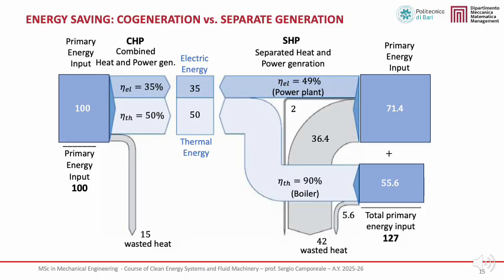As a result, the total primary energy input is approximately 127 units, equal to 71.4 plus 55.6, which is significantly higher than in the cogeneration case. This comparison clearly shows that cogeneration allows a substantial primary energy saving. By producing heat and electricity in a single integrated process, CHP systems reduce energy losses, improve efficiency, and lower environmental impact compared to separate generation.